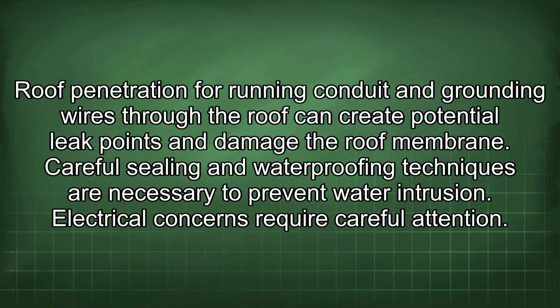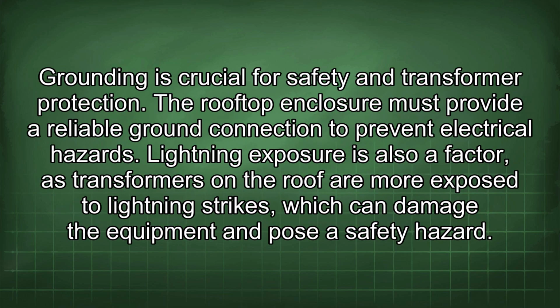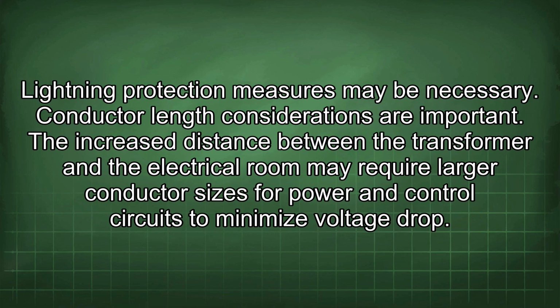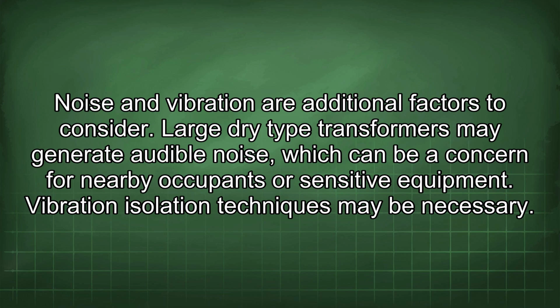Electrical concerns require careful attention. Grounding is crucial for safety and transformer protection. The rooftop enclosure must provide a reliable ground connection to prevent electrical hazards. Lightning exposure is also a factor, as transformers on the roof are more exposed to lightning strikes, which can damage the equipment and pose a safety hazard. Lightning protection measures may be necessary. Conductor length considerations are important. The increased distance between the transformer and the electrical room may require larger conductor sizes for power and control circuits to minimize voltage drop.